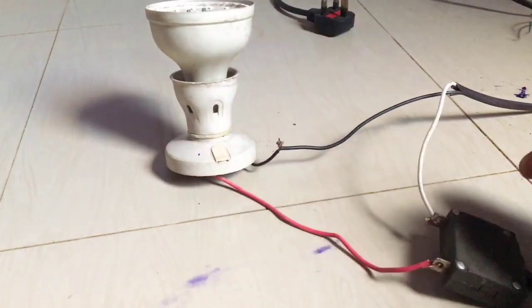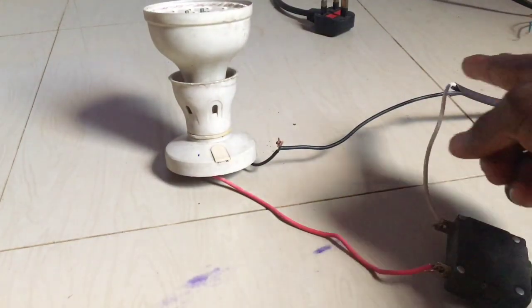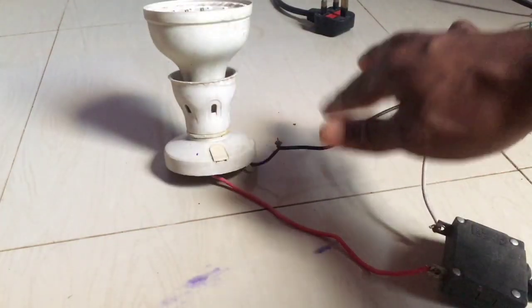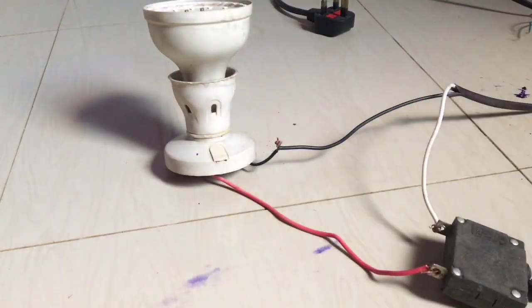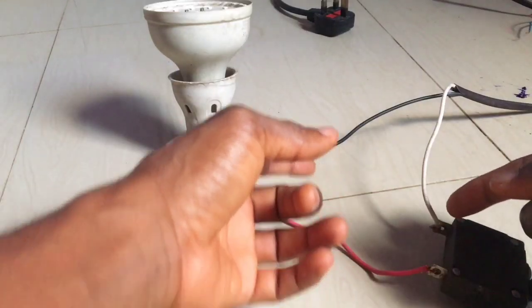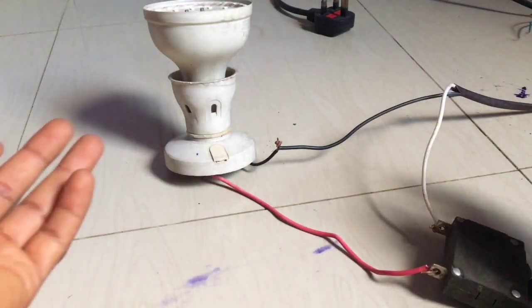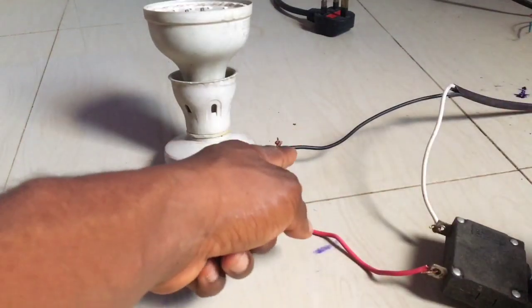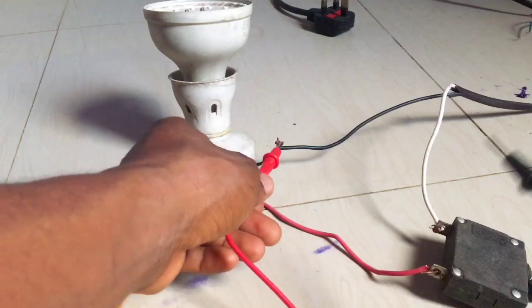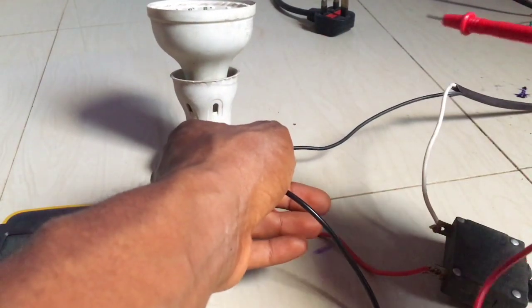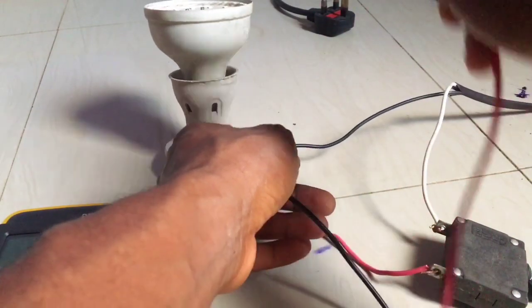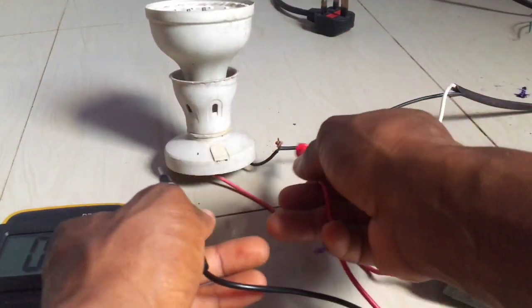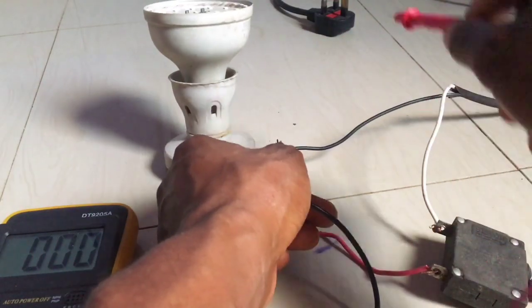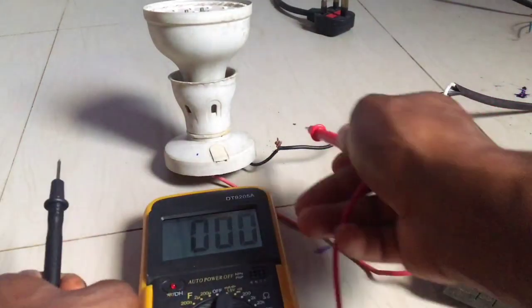The neutral link may be okay, but if this is not in order, it won't work. If the neutral link as well has a fault, it won't work. We already know how to test for voltage across these live terminals, so you can pick neutral from anywhere to confirm that this line is true. To confirm whether the neutral link is okay, you place your voltmeter here at the neutral and test any other live terminal. If it does not give you voltage, then you know that the neutral link is bad. If you keep one probe here and one probe at any other live terminal, and you don't get voltage, then this neutral link is bad.